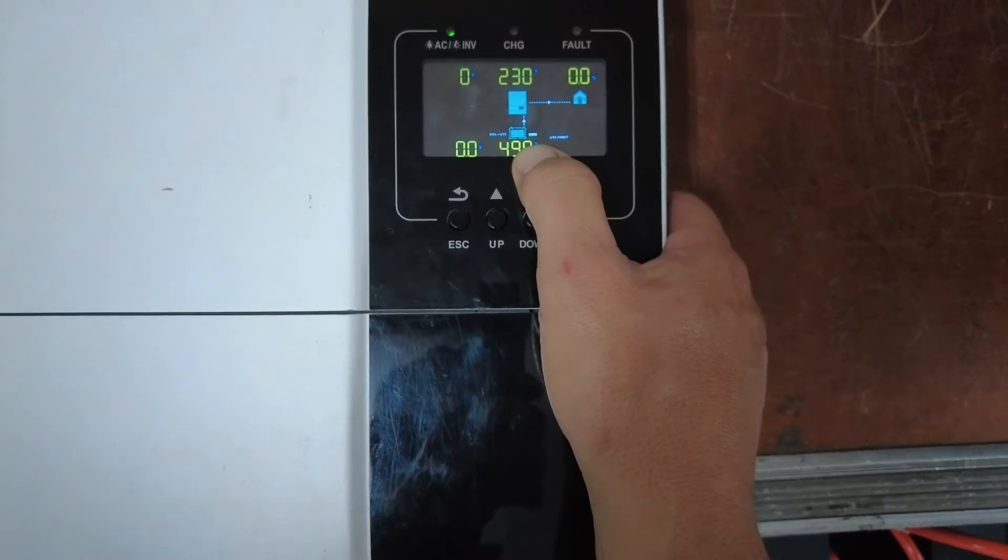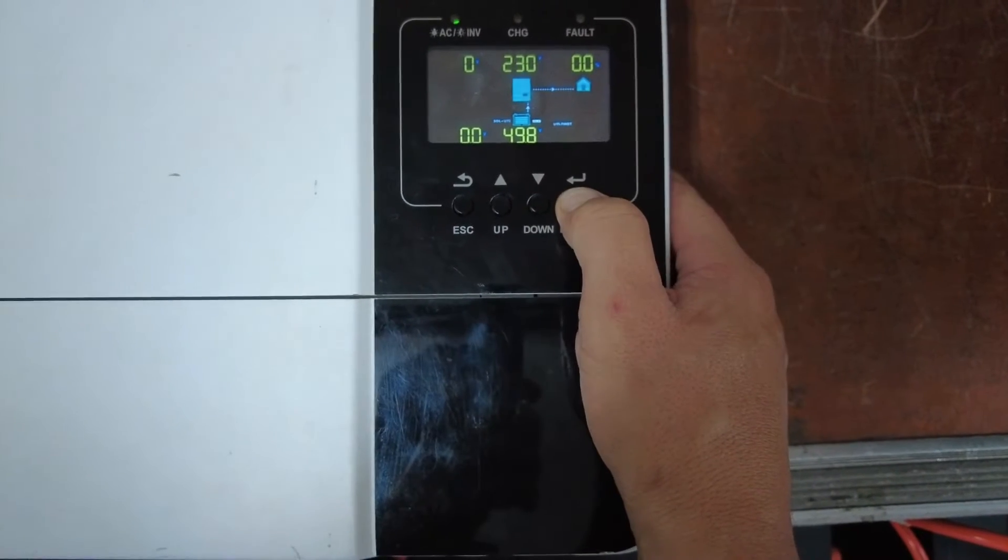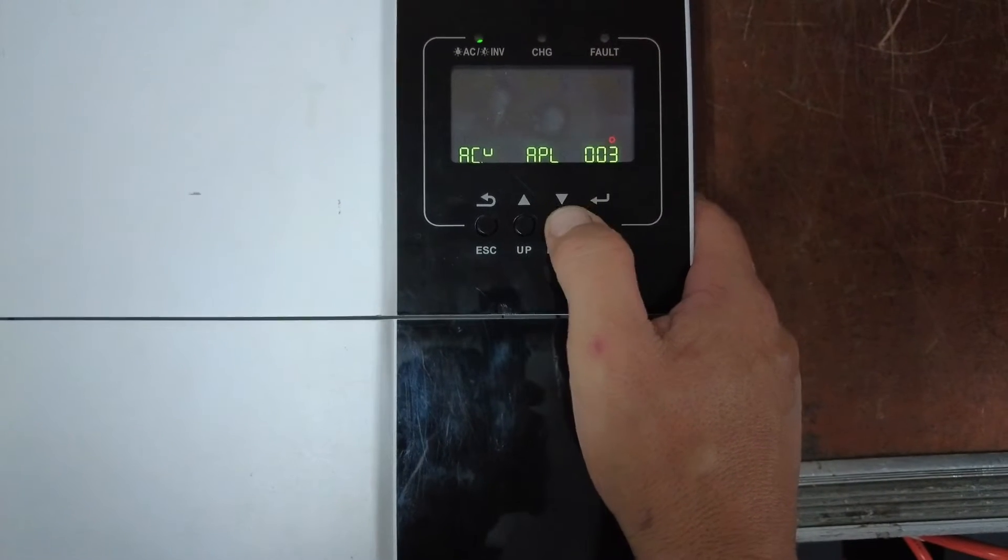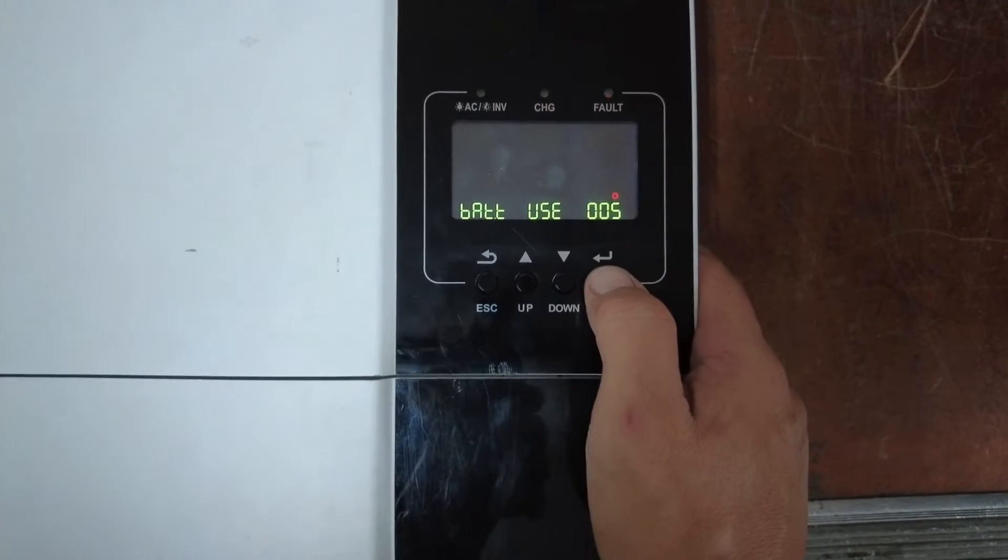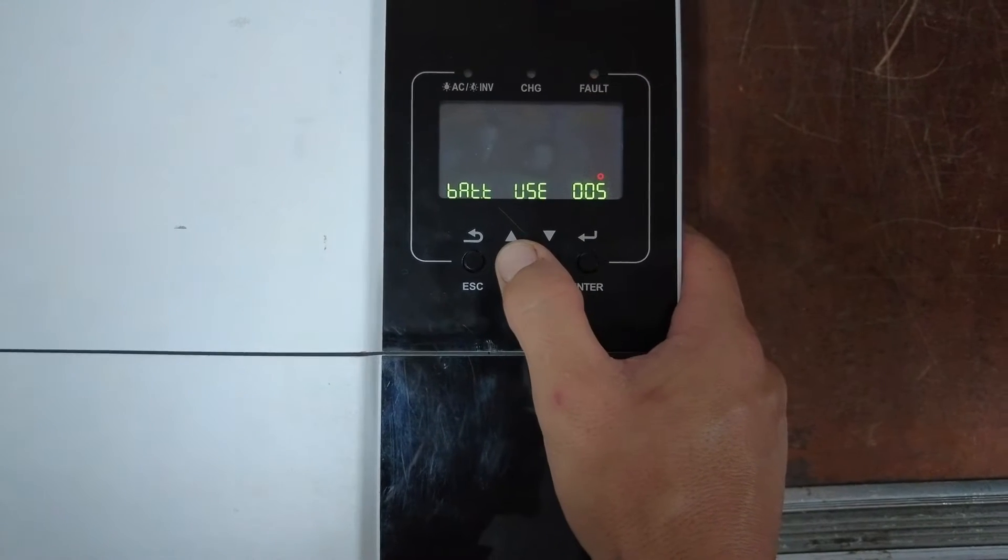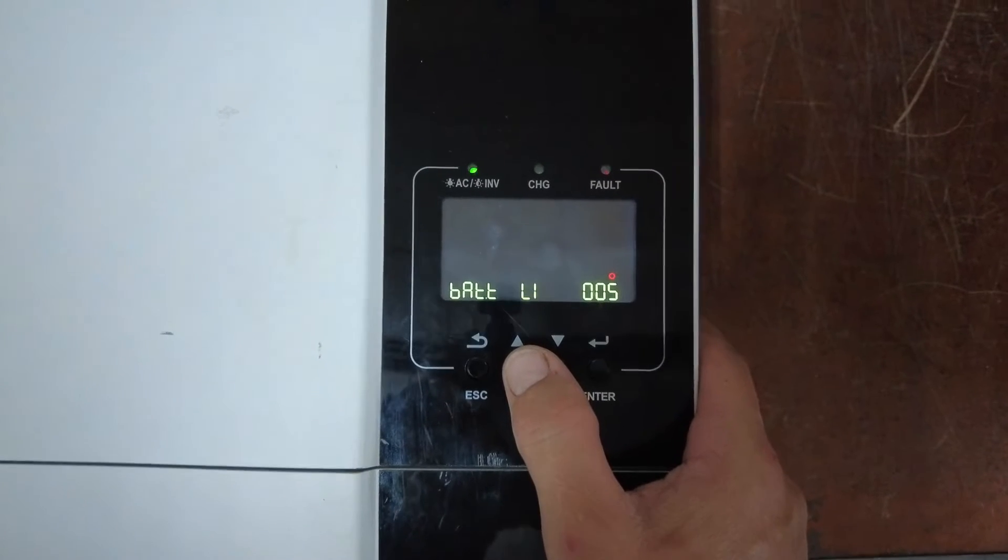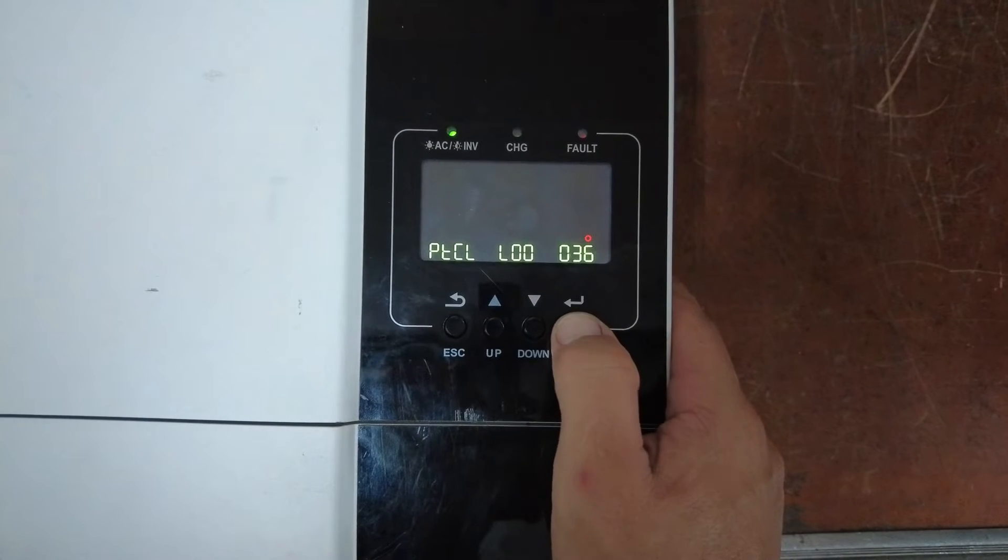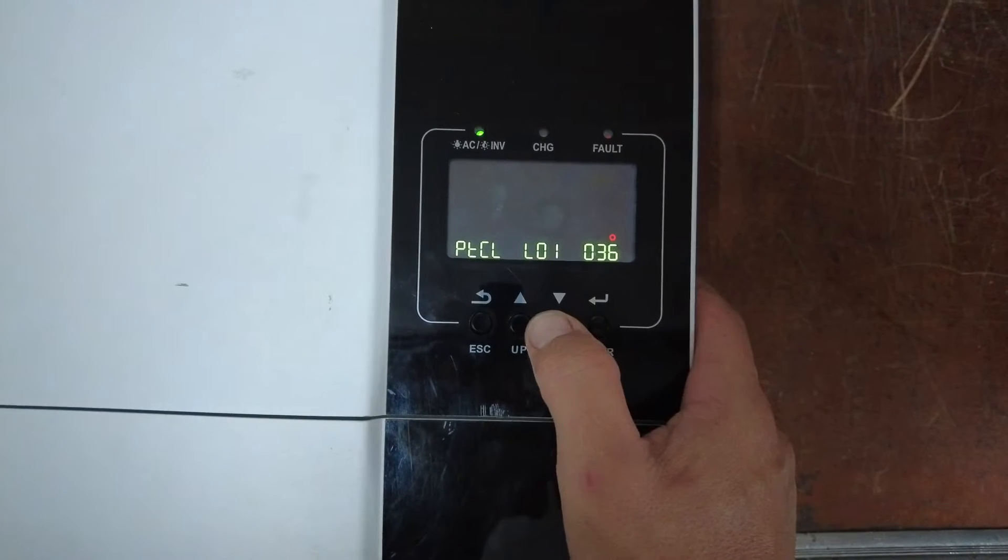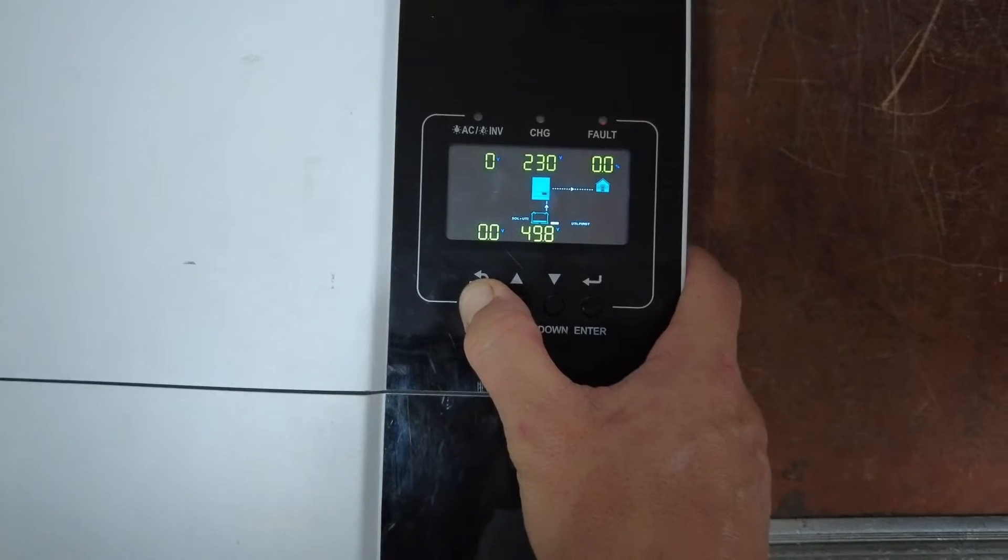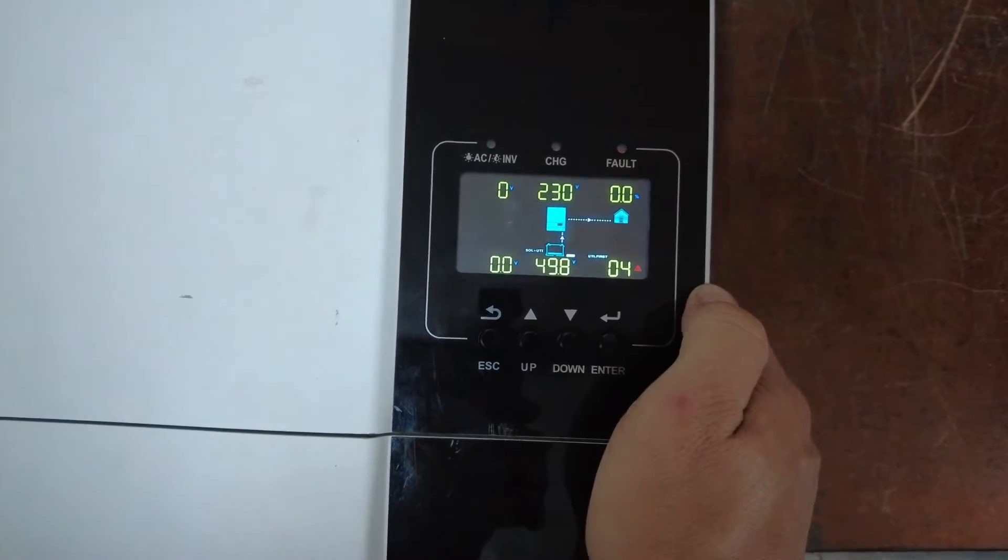We need to change the battery type to lithium. Long press the enter button and go down to setting number 5, which is currently on user defined. Press enter. Using the up and down arrows, we will move until we find the LI icon. Press enter. Enter again. We can set it to L01. Press enter and press escape.